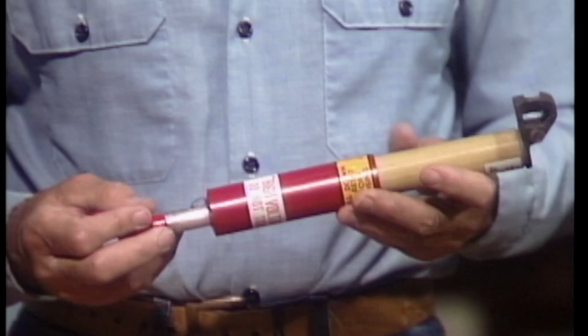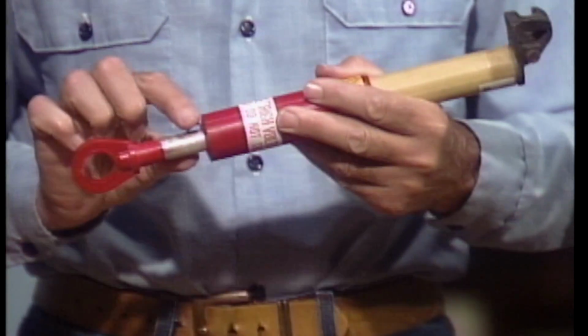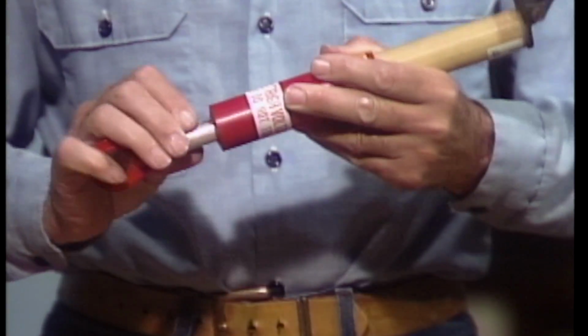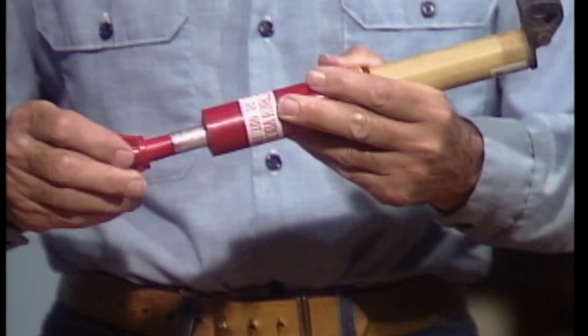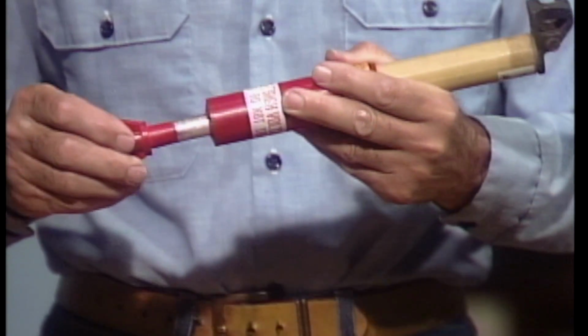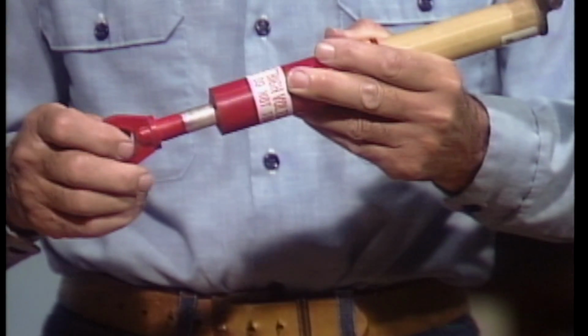Another type of load break device has an arc snuffer on the fuse barrel. When the fuse door is closed, the spring is tripped. The door is primed so that when it's open, a non-conductive outer tube slides over the fuse contact point, snuffing the arc that may be forming.